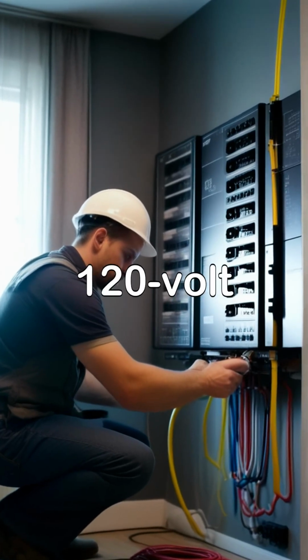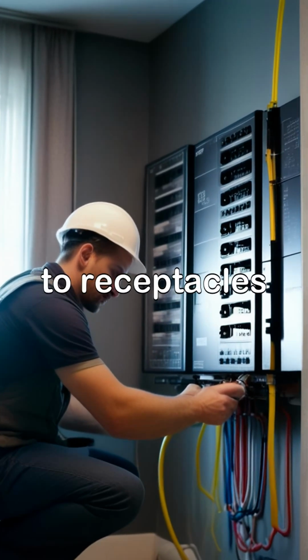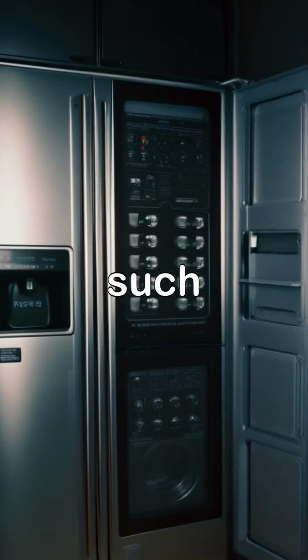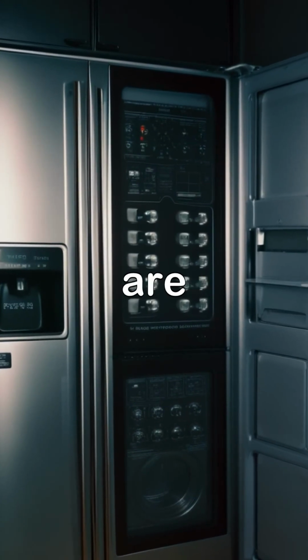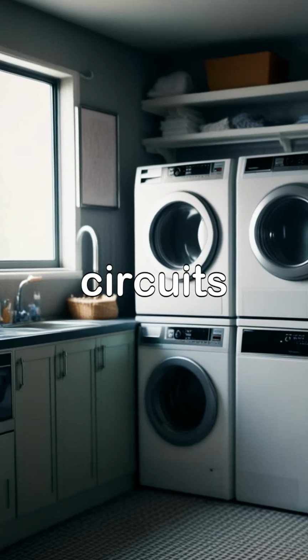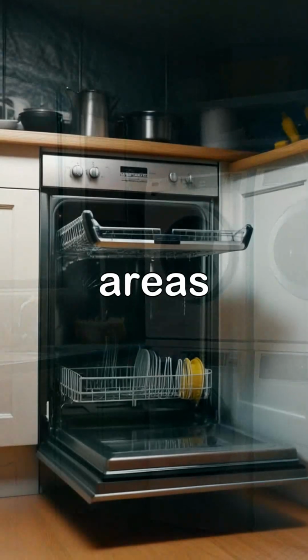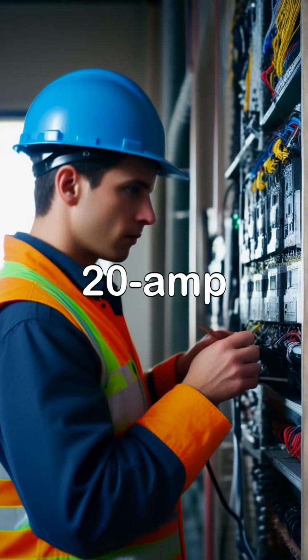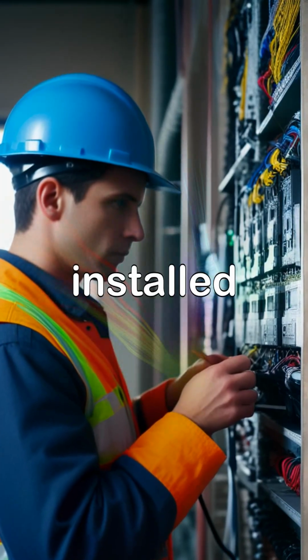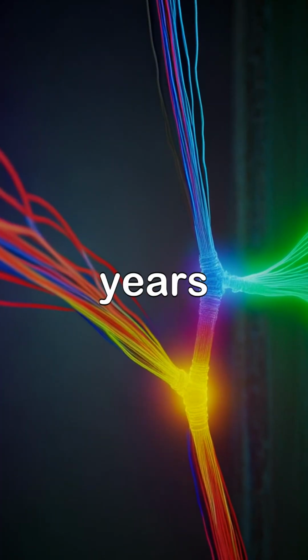Small appliance circuits. These 120-volt circuits supply power to receptacles to which small appliances such as toasters and food processors are to be connected. Typically, these circuits are restricted to kitchens and eating areas. A minimum of 2 such 20-amp circuits are routinely installed in kitchens built within the last 30 years.